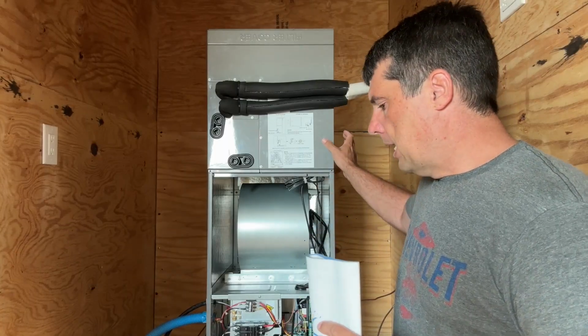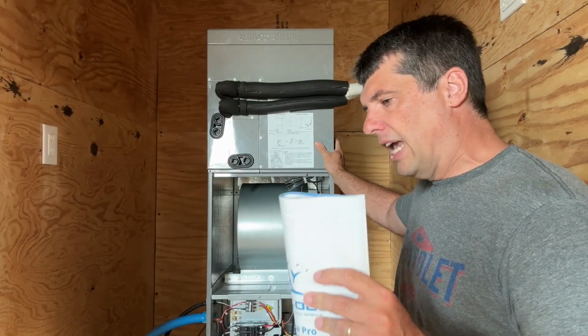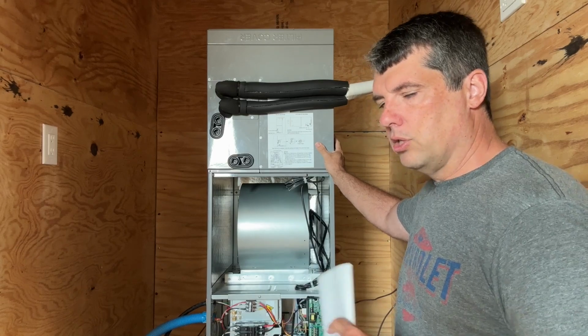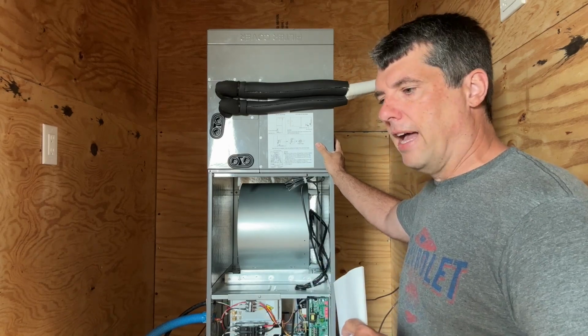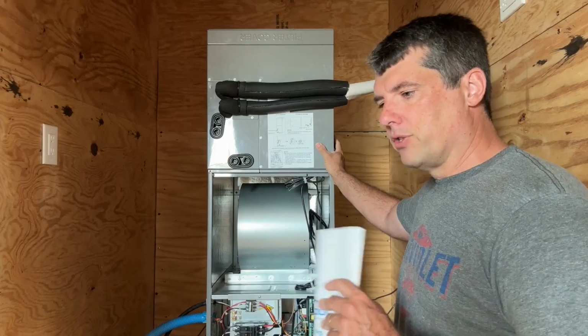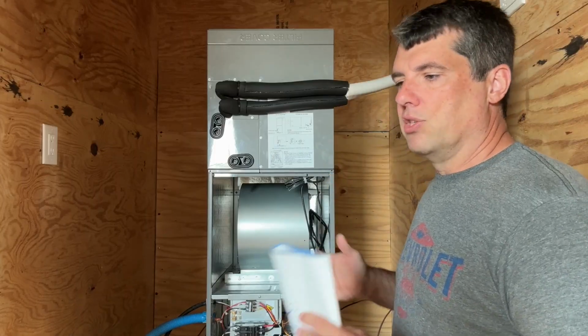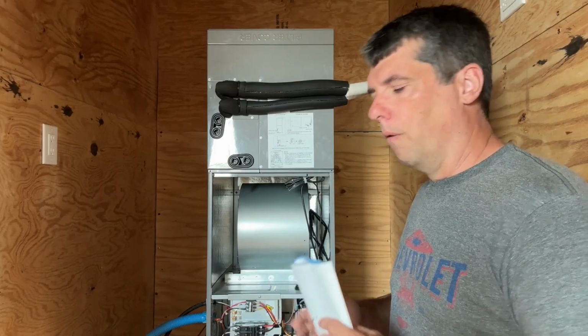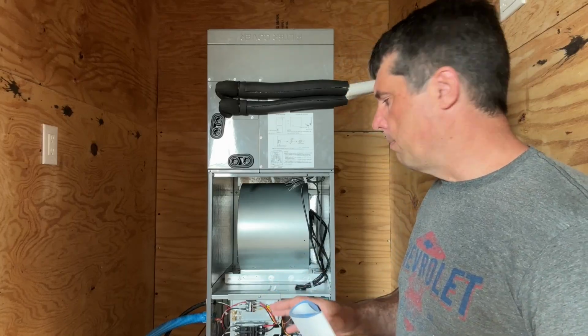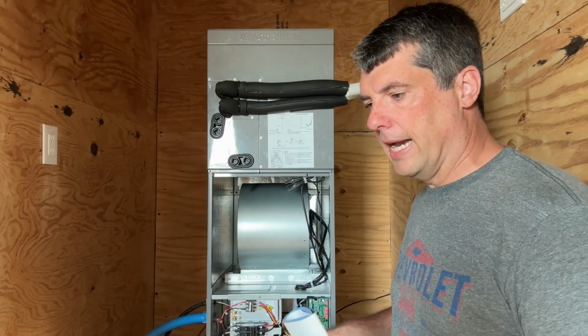This is a heat pump that heats and cools, so we're using this to do both. It has a reversing valve that flips the refrigerant inside the lines based on what you want to do, either heat or cool. So that is very important when it comes to wiring the thermostat.